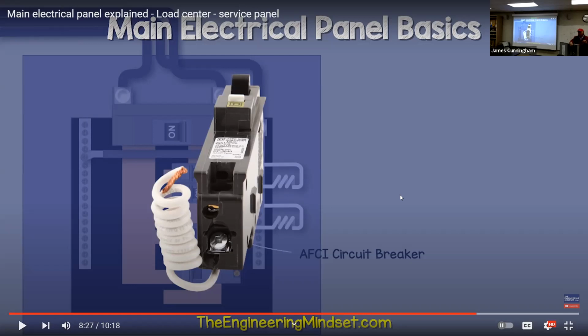What arc faults do is, when it senses a short between the hot and the neutral, it pops the breaker and stops it before a fire can actually start. So when the insulation on that extension cord got to the point where it would start melting and short out, it would pop the breaker before it had a chance to really start sparking and catch on fire. And that's what arc faults basically do.